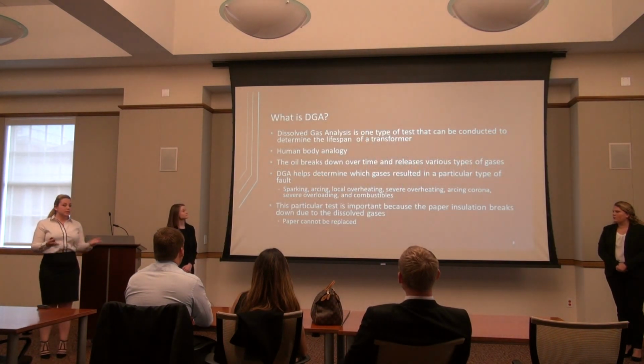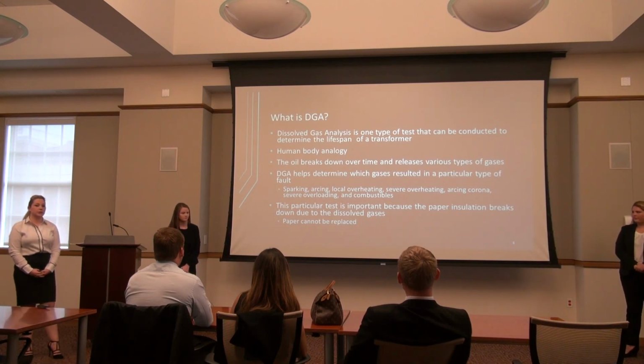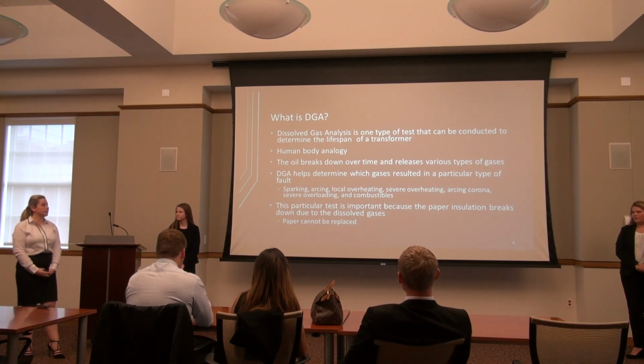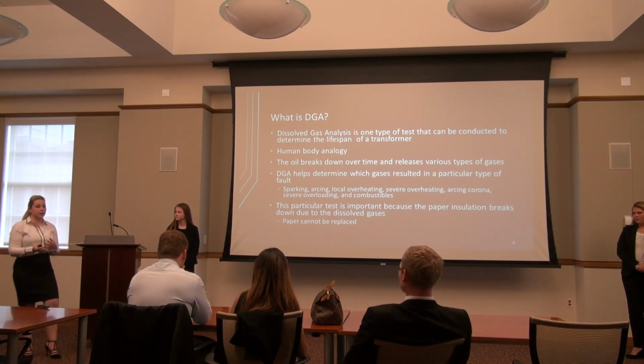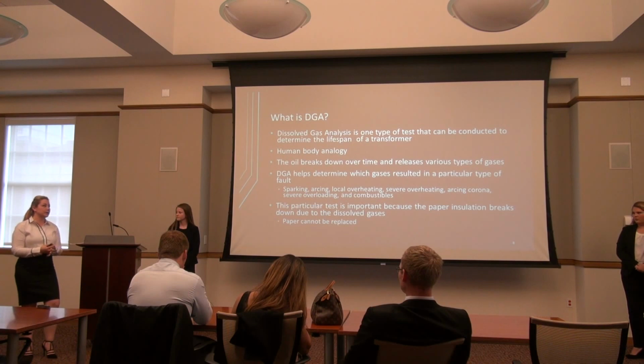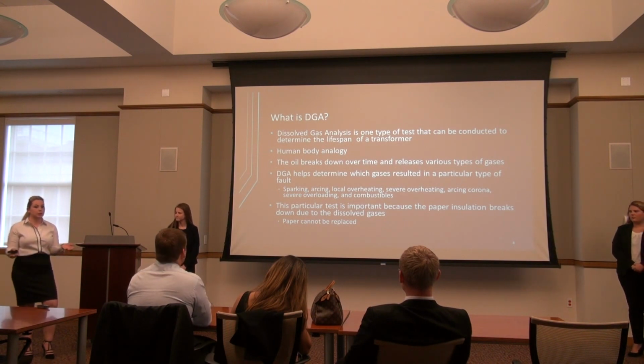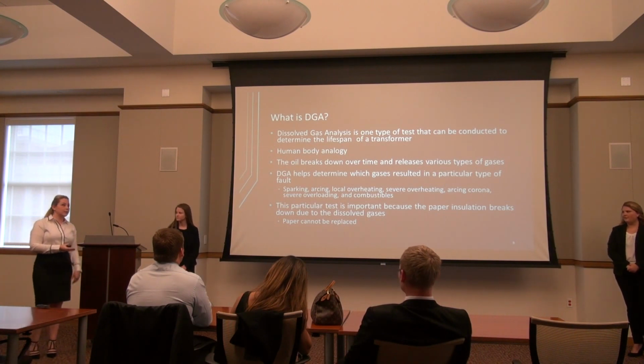So dissolved gas analysis, or we'll refer to it as a DGA from now on, is just one type of test that can be conducted on a transformer, and you can think of a transformer as a human body and the oil as blood. So the DGA is kind of like a blood test for a transformer. Over time, the oil breaks down and releases various types of gases, and from these different gas combinations, we can determine the types of faults that occur. There are various faults: sparking, arcing, overheating, etc. These can create severe issues within a transformer and prevent it from functioning at its highest capacity. These problems can even cause a transformer to blow up in some extreme cases.